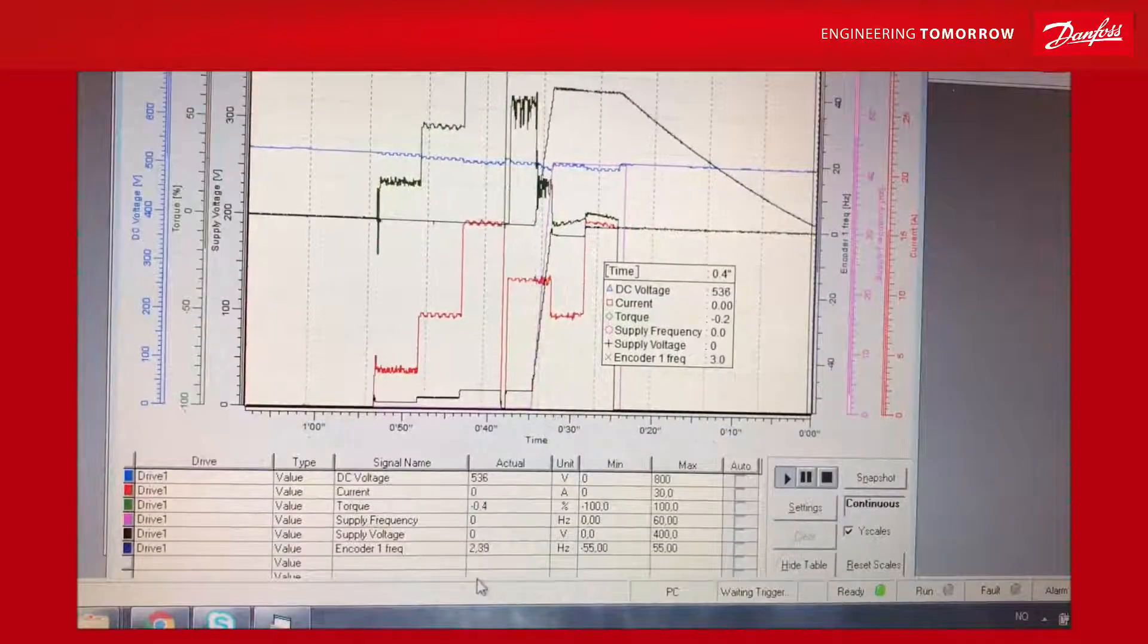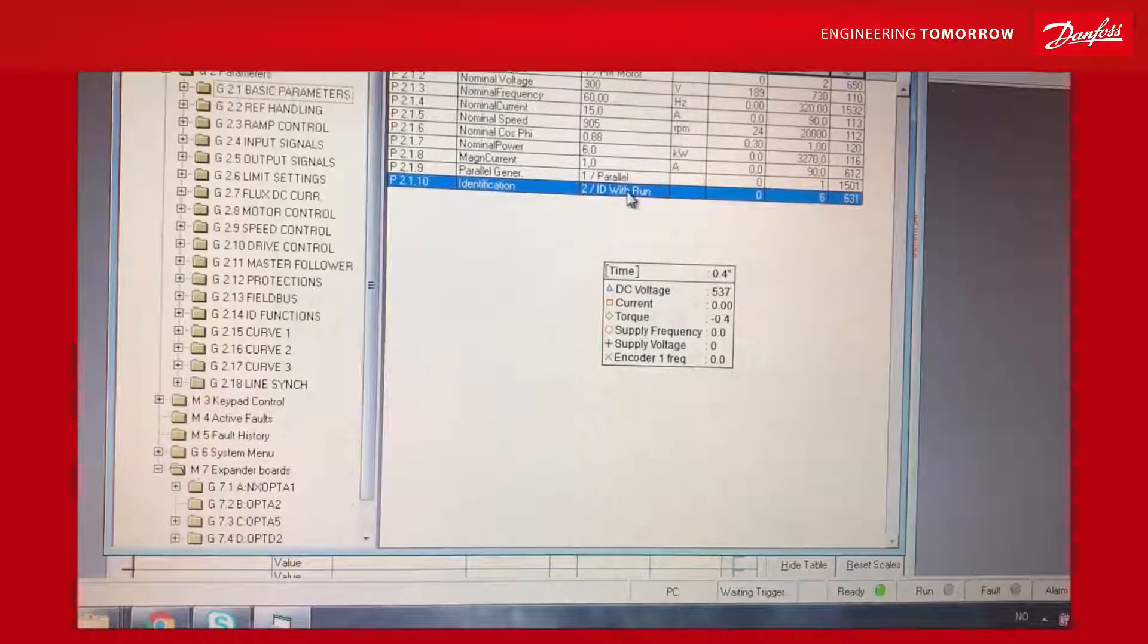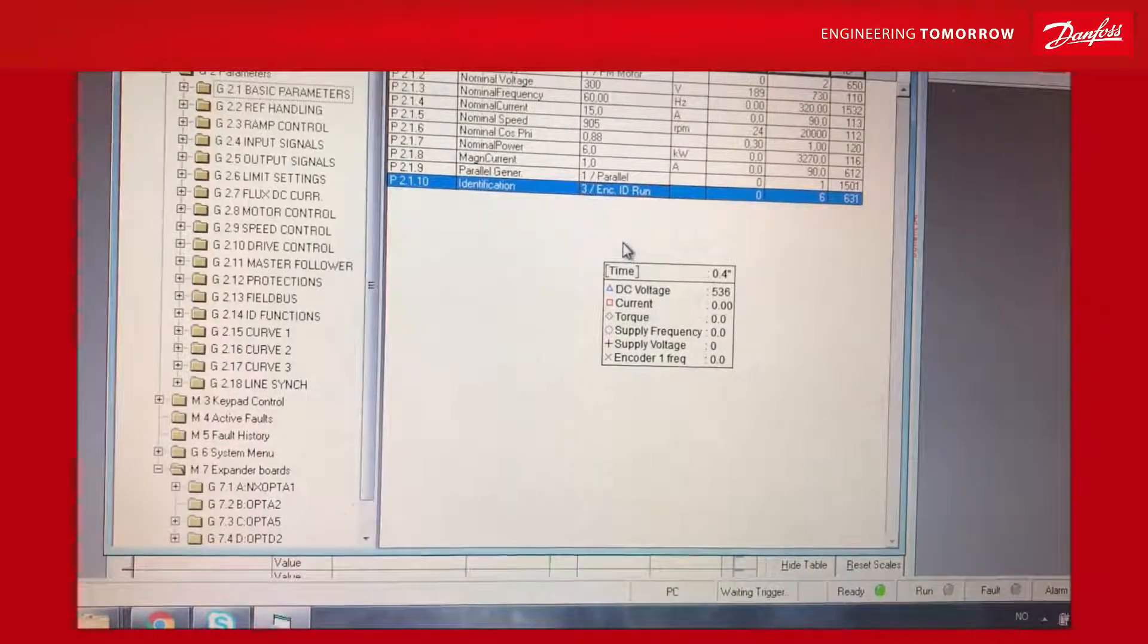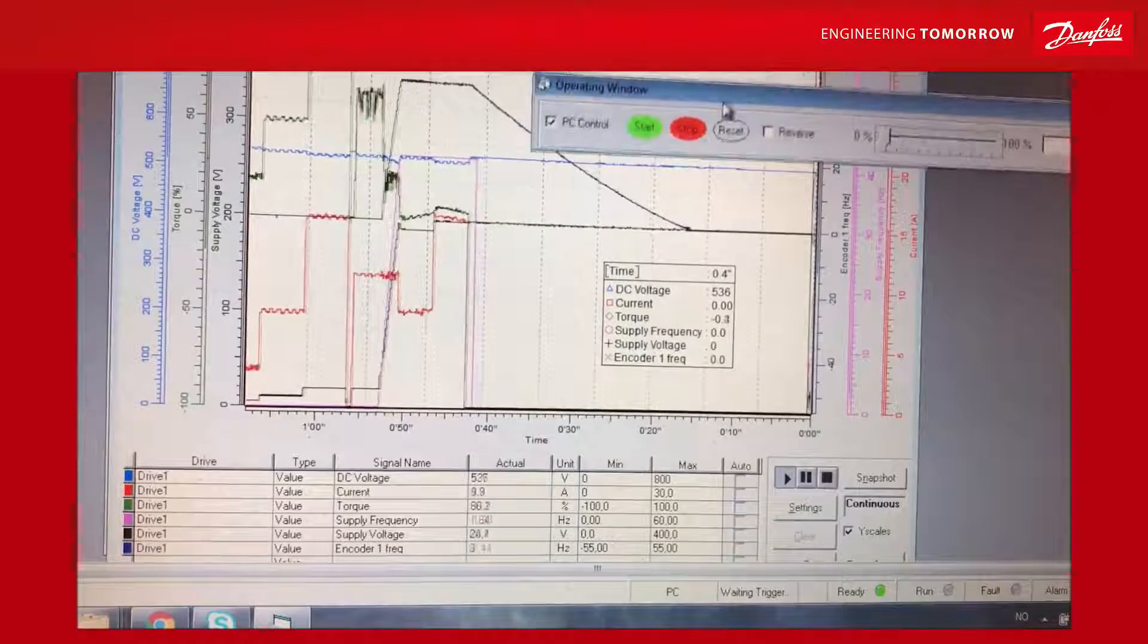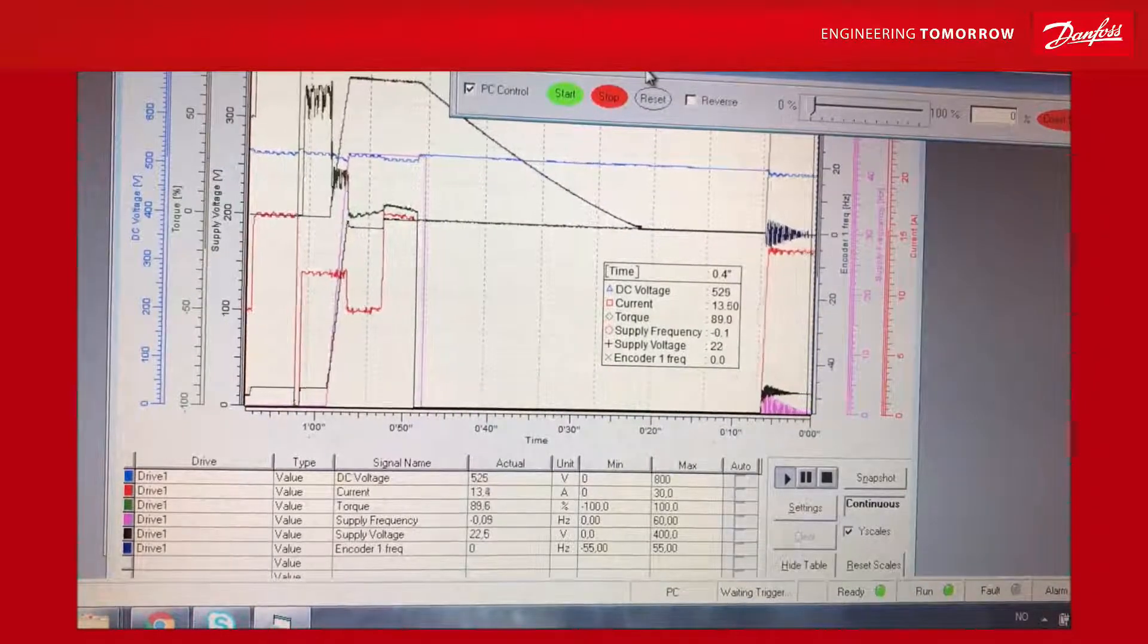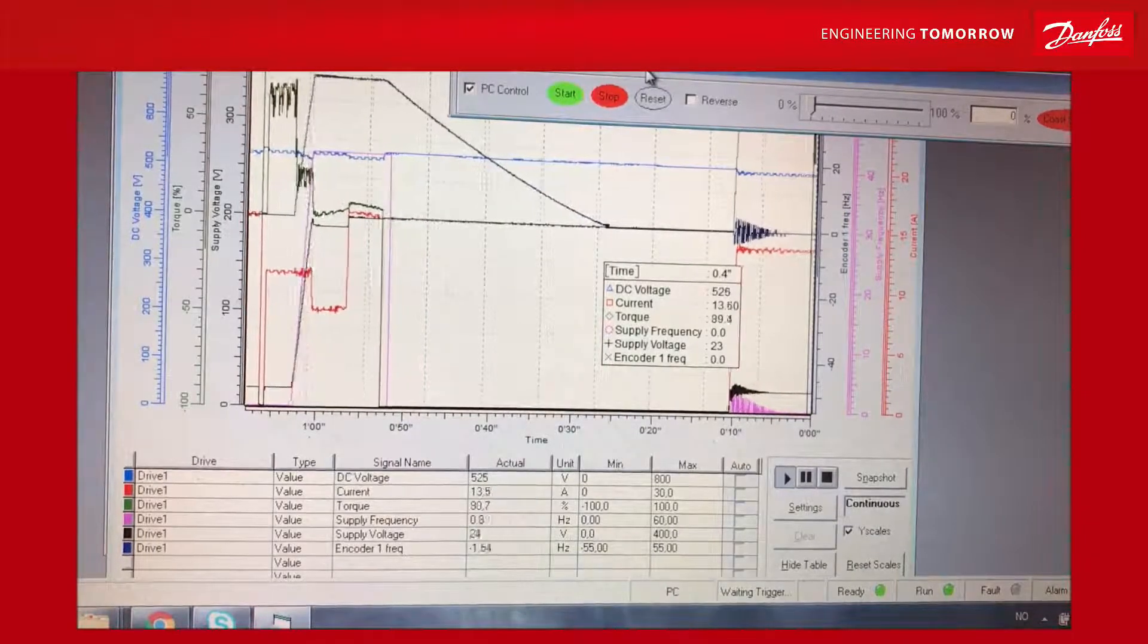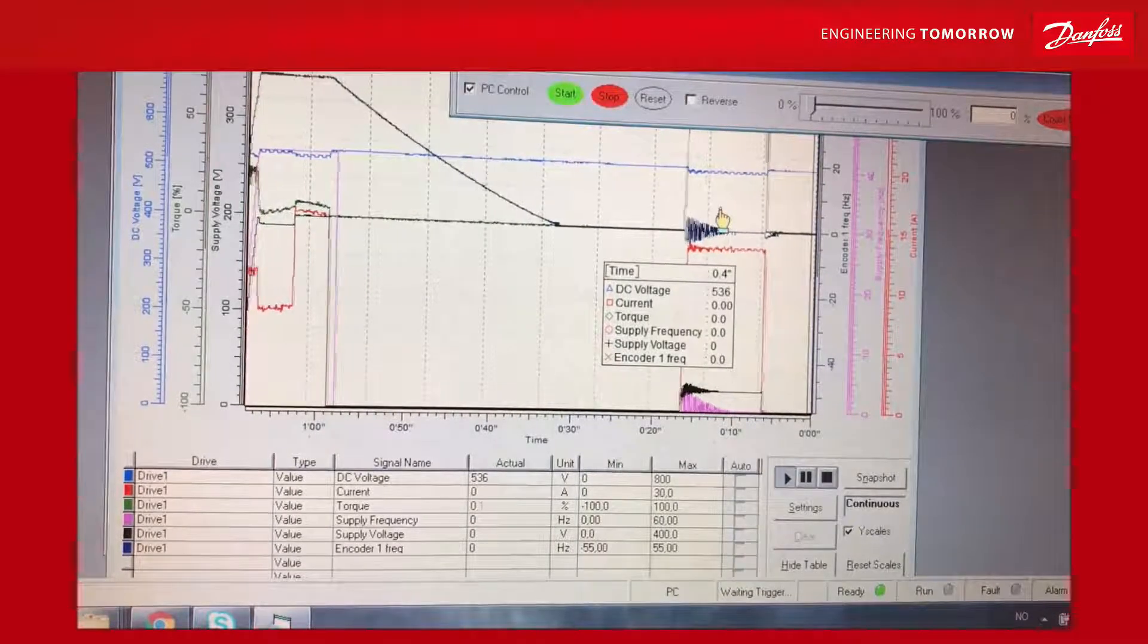The next step is to verify the encoder signal. We go to identification, then to no action. I select encoder ID run. The purpose of this is to find the Z pulse. I hit the start button and it starts doing this strange movement. That is the stator field sweeping over the rotor magnets to find the magnet and its relation to the Z pulse of the encoder.